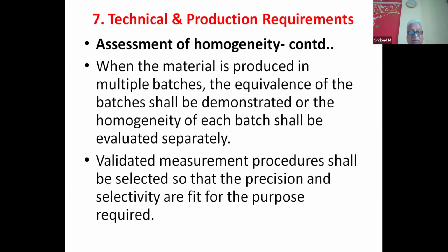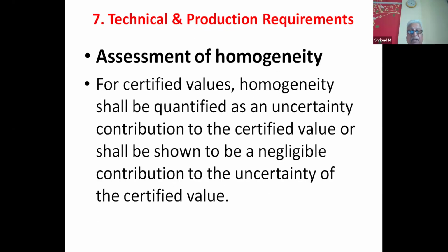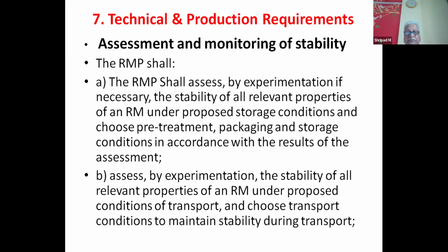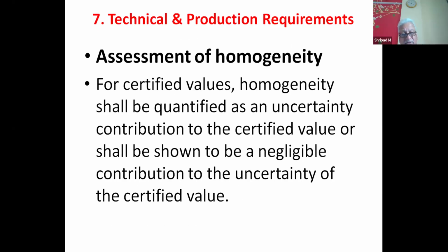Validated measurement procedure shall be selected so that precision and selectivity are confirmed to be fit for the purpose requirement. So for certified values, homogeneity shall be quantified as an uncertainty contribution. Yes, homogeneity has to be taken as an uncertainty contribution to the certified value, and it shall be negligible, meaning as low as possible. The uncertainty from the assessment of homogeneity should be as minimum as possible.